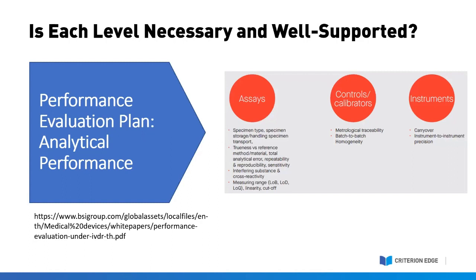Again, I refer you to BSI, who's provided some really helpful insights in one of their recent white papers. The APR is expected to address three main areas. That's the assays, so justifying the specimen type, the storage and handling, the transport, but then also the accuracy of the test in terms of the analytical performance. So these can be things such as trueness, but it's important to make note of the reference methodology that's being used. It can also be repeatability and reproducibility, analytical sensitivity, interference or cross-reactivities that you've identified, as well as the range for which measurements can be accurately made. So this can include things like linearity and also the limit of detection or the limit of quantification, if appropriate, as well as cutoff values.